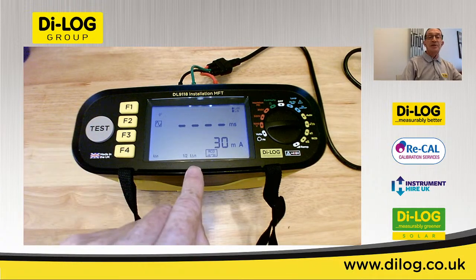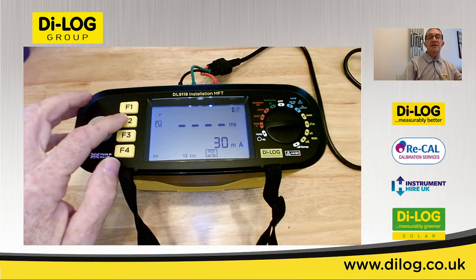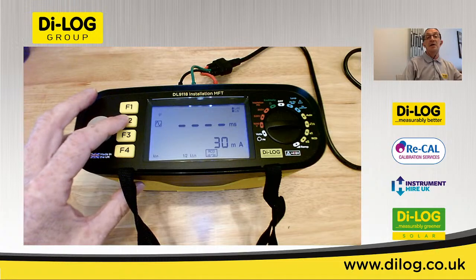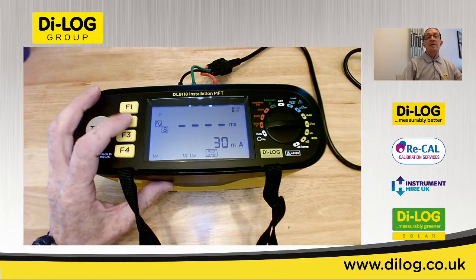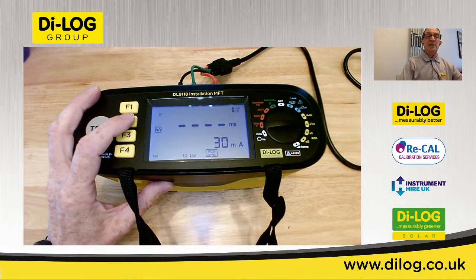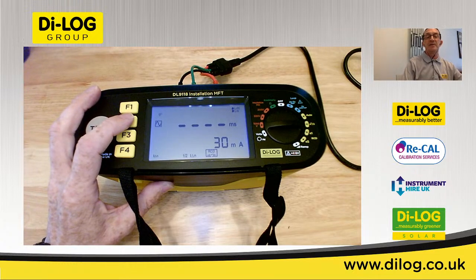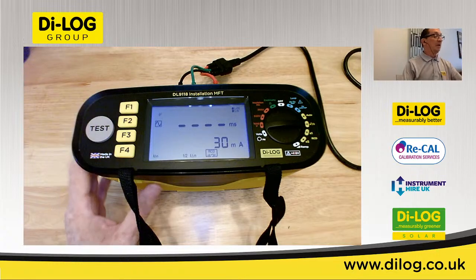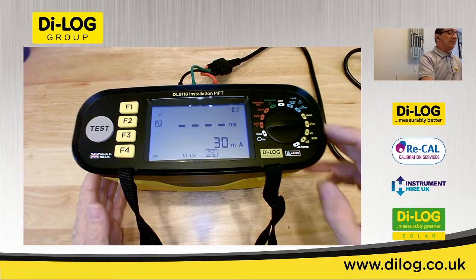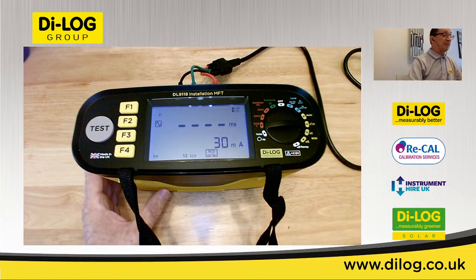So we've got visual indication at the bottom of the screen as the type of test I'm carrying out, and the left hand side is the type of RCD that we're testing. So we've got our regular AC, we've got AC selective, we've got DC sensitive, and we've got DC selective, and then back to AC again. So as mentioned, we've got the half times, the times 1 and the times 5 your fast trip test.